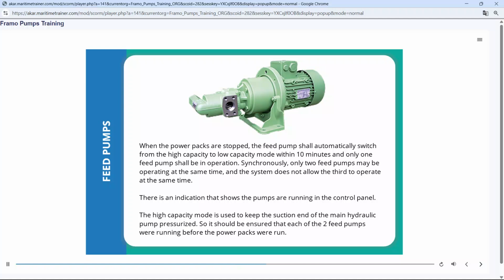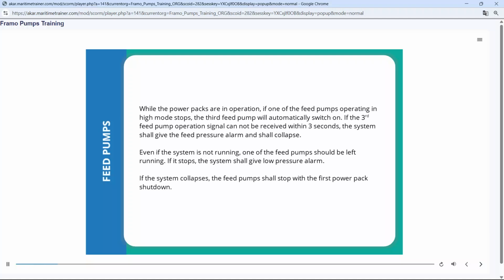There is an indication in the control panel that shows the pumps are running. The high capacity mode is used to keep the suction end of the main hydraulic pump pressurized. So it should be ensured that each of the 2 feed pumps is running before the power packs are on. While the power packs are in operation, if one of the feed pumps operating in high mode stops, the third feed pump will automatically switch on.